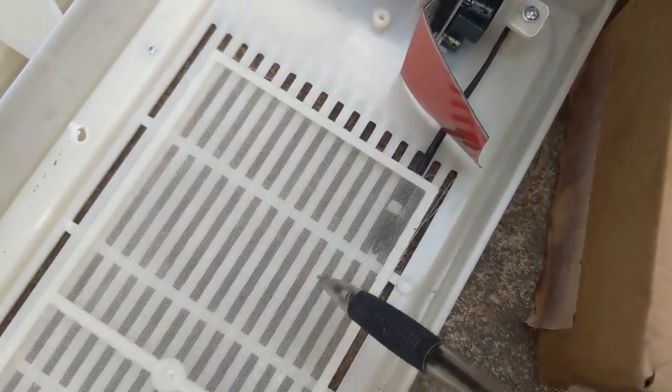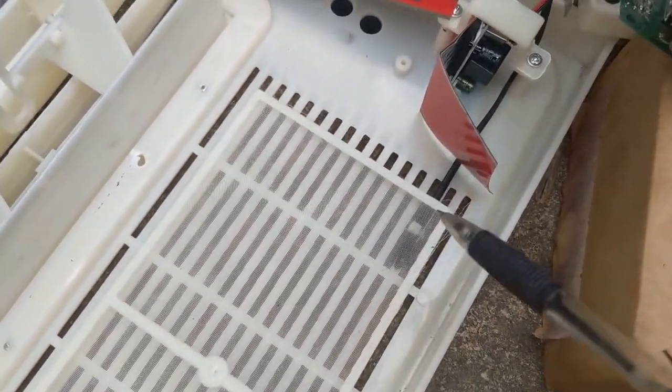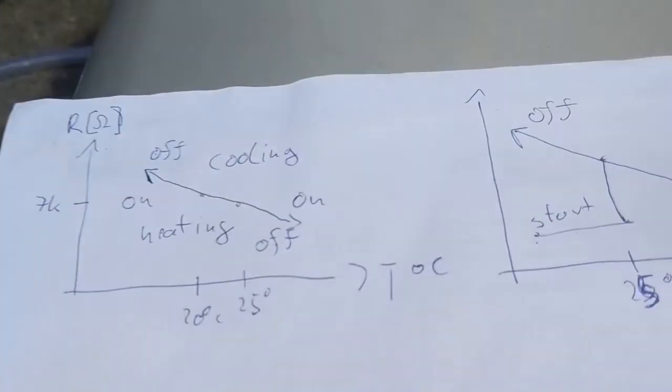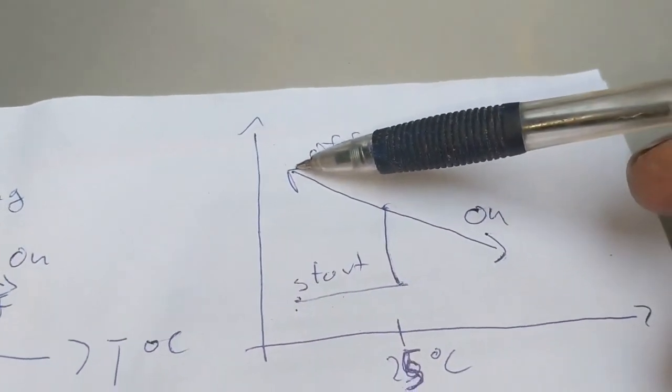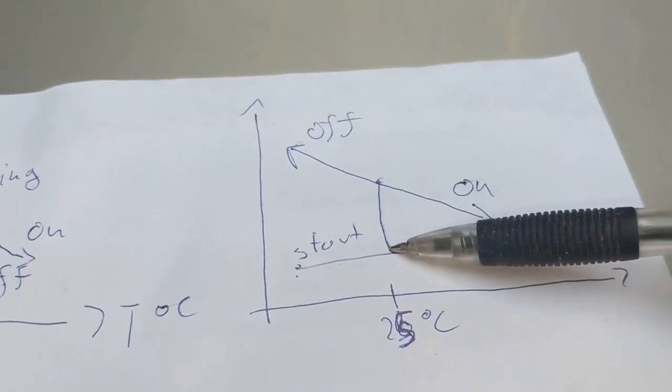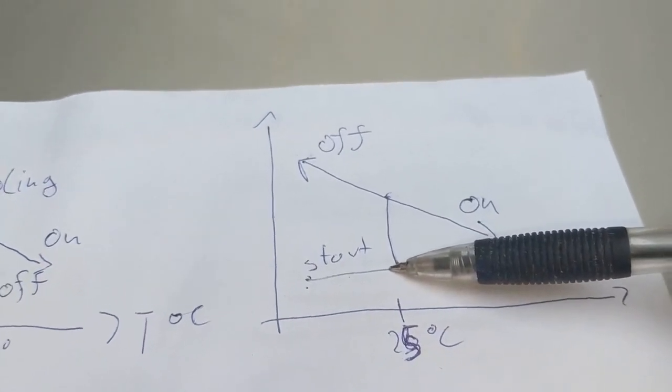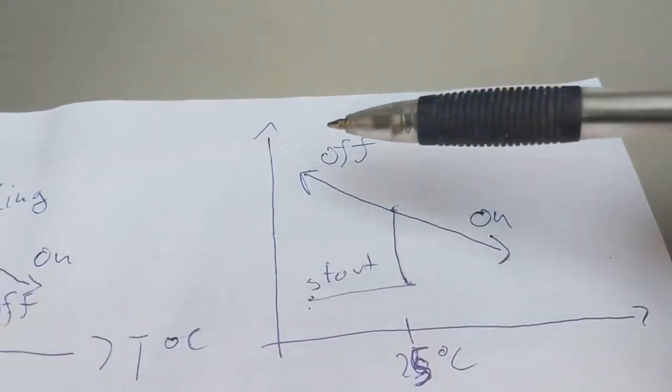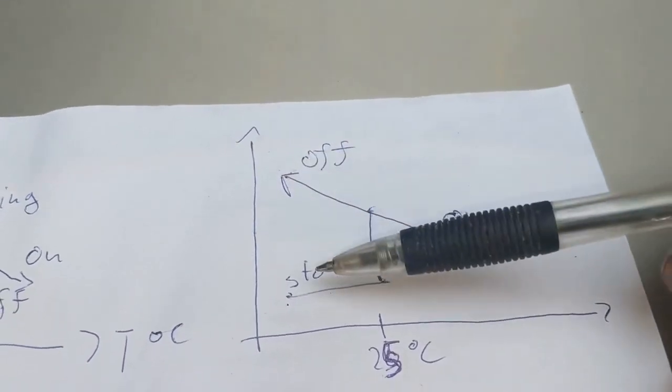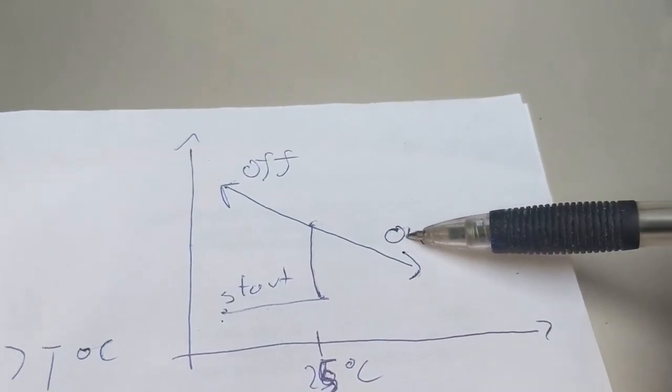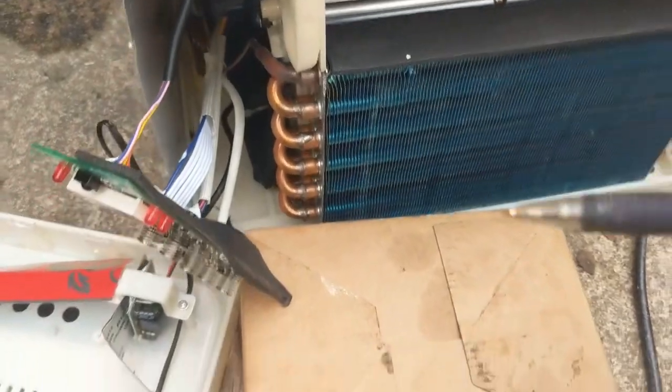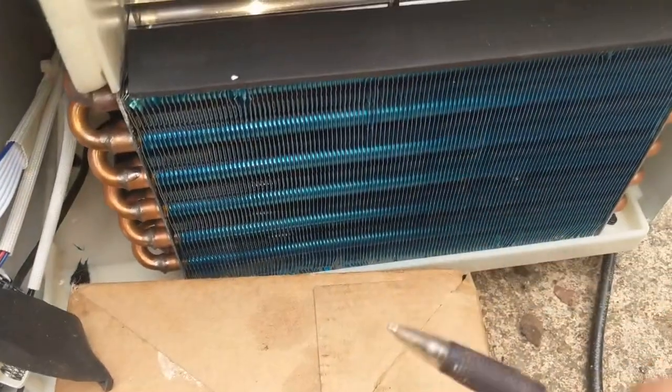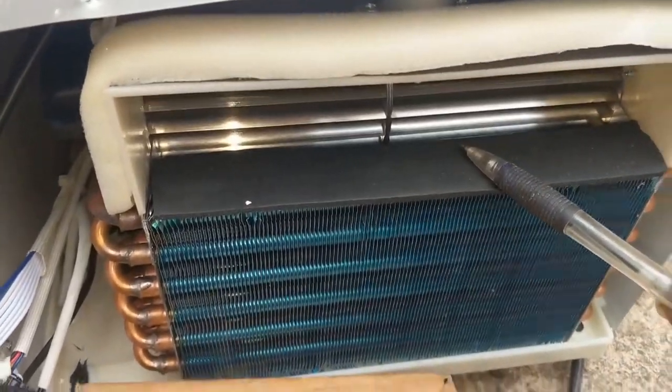This will be the outside, and let's say it's 0 degrees outside, so it will be 10 kilo ohm, and at 10 kilo ohm the machine will be shut off. But if I then, here with the switch, put another 10 kilo ohm in parallel, this will drop from 10 kilo ohm to 5 kilo ohm. The machine will think it's very hot and will start the heat pump, making this 0 degree even colder. Let's see if this works.